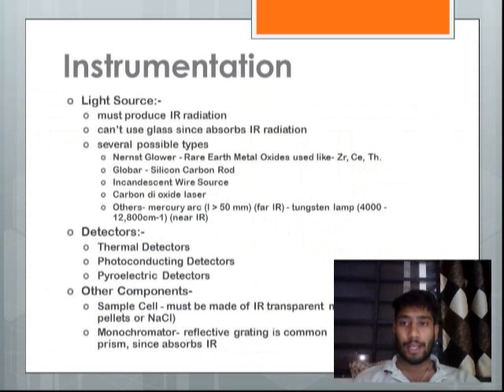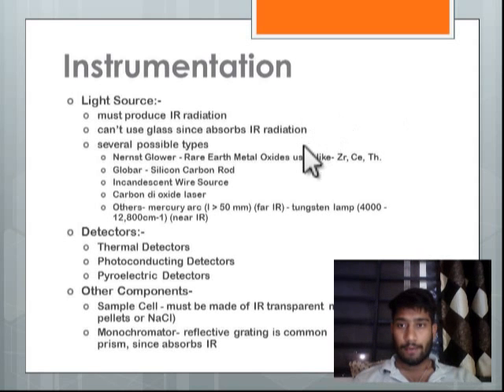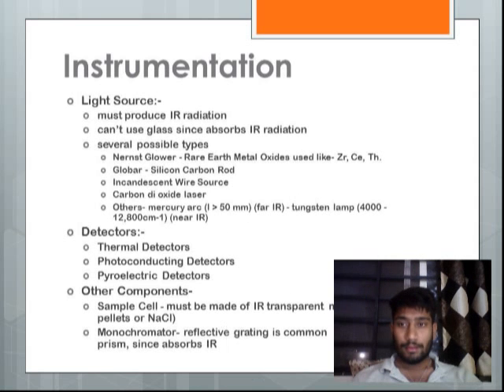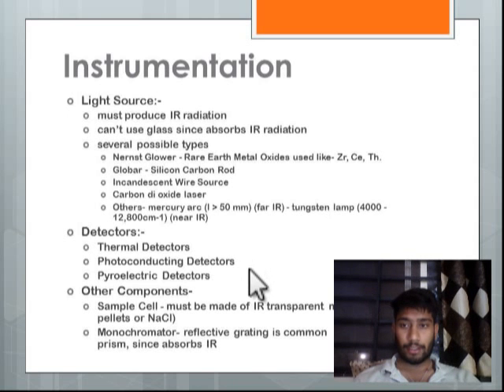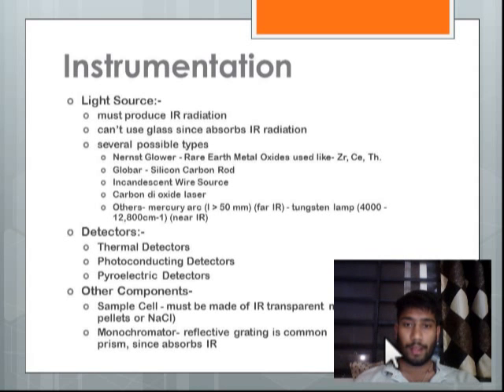Here is the instrumentation of IR spectroscopy. First is the light source, which must produce IR radiation. Glass cannot be used since it absorbs IR radiation. Several possible types of light sources are used: rare earth metal oxides such as zirconium, cerium, and thorium; a globar silicon carbon rod; wire source; carbon dioxide laser; and mercury arc. Detectors include thermal detectors, photoconducting detectors, and pyroelectric detectors. Other components such as the sample cell and monochromator are also necessary in the instrumentation.